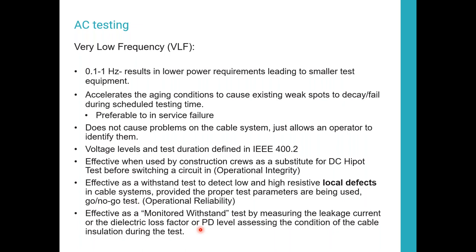go, no-go test threshold. And it can be effective as a monitored withstand test by measuring the leakage current or the dielectric loss factor. You can monitor where your PD starts and fails. Okay, so you know where you are with respect to your operating voltages. Valuable to know. With the monitored systems, you can actually also detect location, and we'll get into that in a little bit also. But it gives you the ability on a cable to determine where on that cable the PD is happening to help repair that cable.